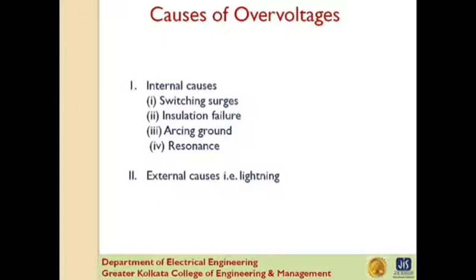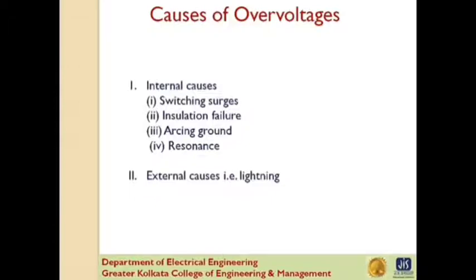Causes of overvoltage. The overvoltages of a power system may be broadly classified into two categories: internal causes and external causes. Internal causes are classified into switching surge, insulation failure, arcing ground, and resonance. External causes are due to lightning. Internal causes do not produce surges of large magnitude. Experience shows that surges due to internal causes hardly increase the system voltage to twice the normal value and are generally taken care of by providing proper insulation to the equipment.